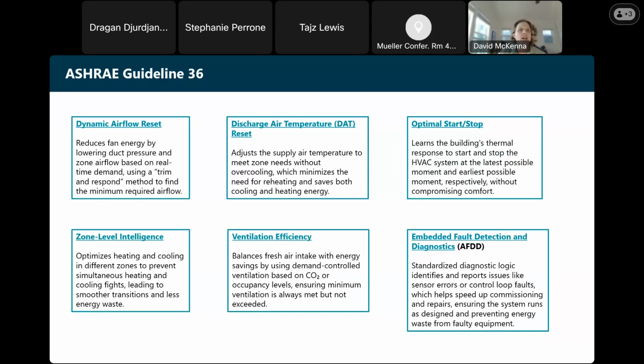So what we're looking at here are some examples of the software side of things. These are some of these sequences, for instance, fault detection and diagnostics. These are things that are primarily ventilation efficiency. A lot of these are going to be driven by the back end or the software of your building management system, or BMS. And so, with this, we can look at, for instance, ventilation efficiency.